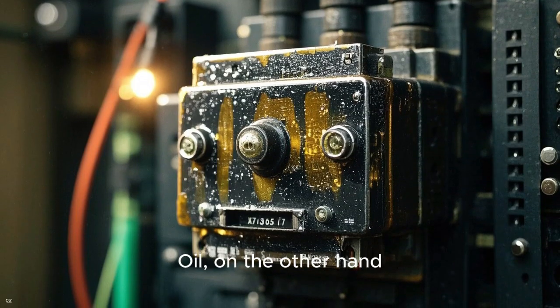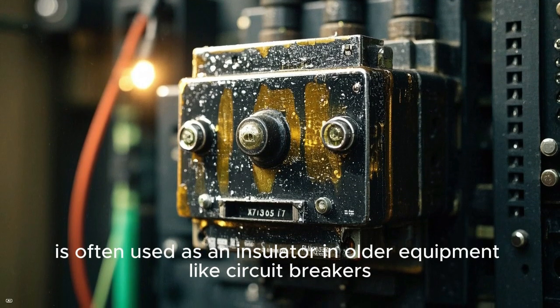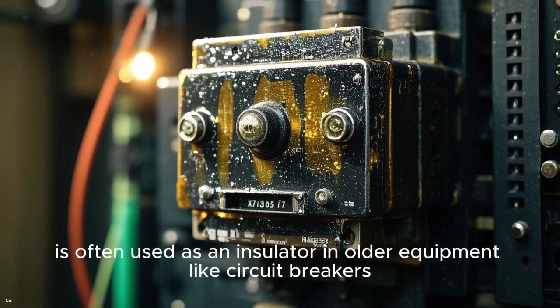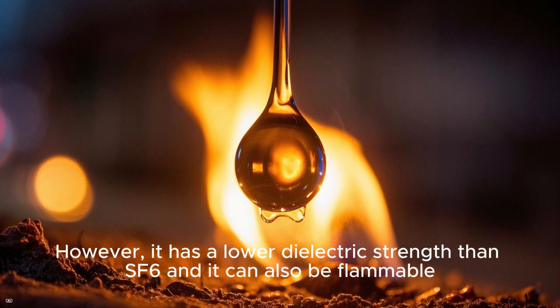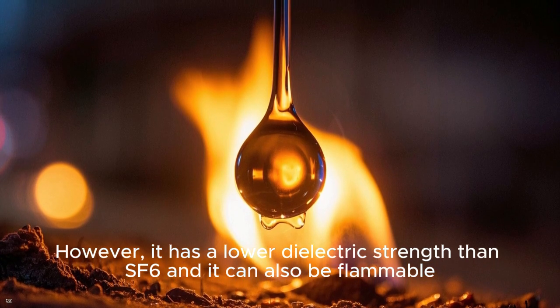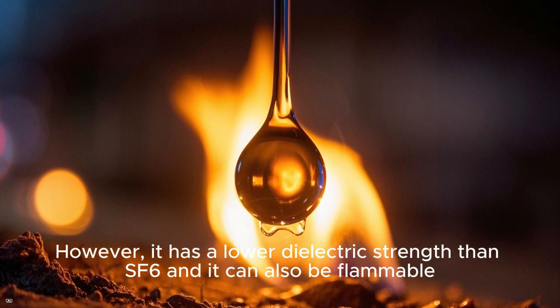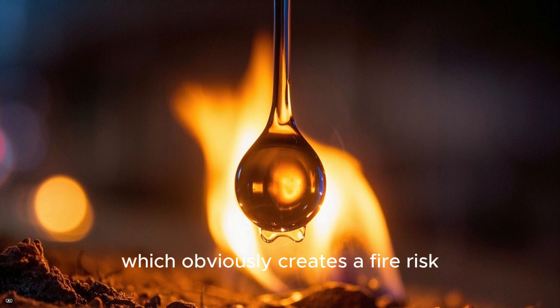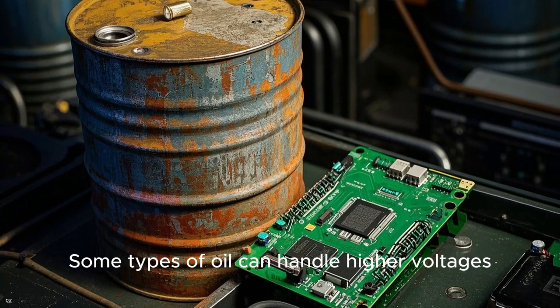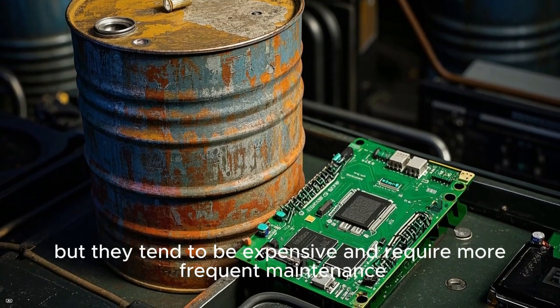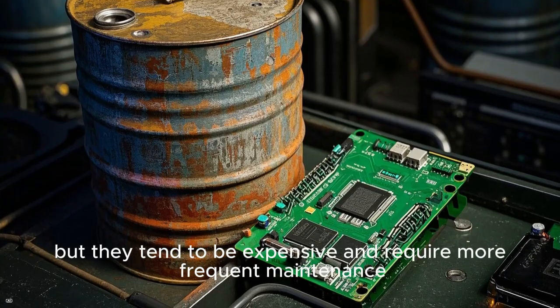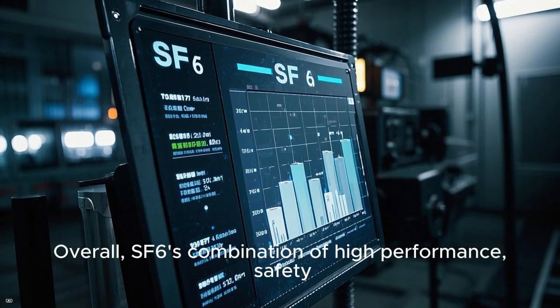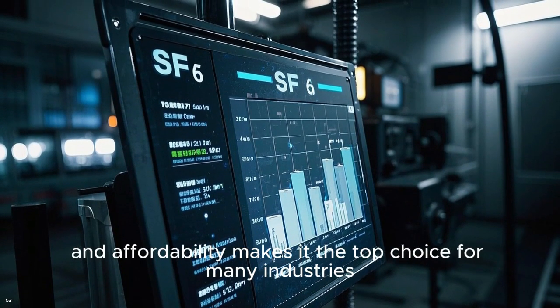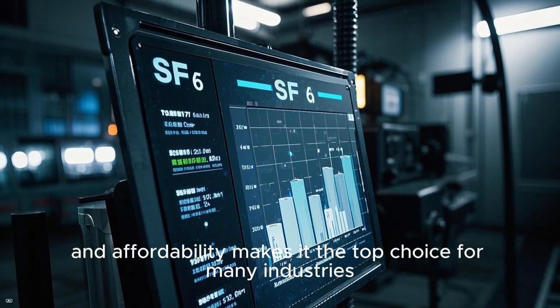Oil, on the other hand, is often used as an insulator in older equipment like circuit breakers. However, it has a lower dielectric strength than SF₆, and it can also be flammable, which creates a fire risk. Some types of oil can handle higher voltages, but they tend to be expensive and require more frequent maintenance. Overall, SF₆'s combination of high performance, safety, and affordability makes it the top choice for many industries.